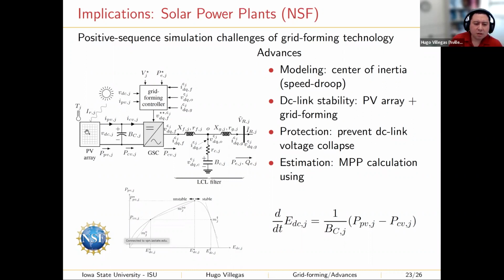So it turns out when the grid side converter is working in grid forming mode, there could be instances when the PV array cannot provide enough power to supply the demand of the grid side converter. At those times, the voltage of the capacitor can suddenly drop and then lead to a voltage collapse. If the DC link voltage collapses, then synthesizing AC voltages at the terminals of the grid side converter is not possible anymore. So this leads to instability problems actually in the grid.